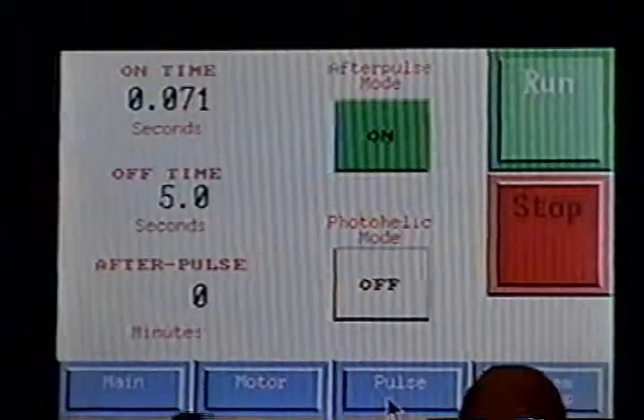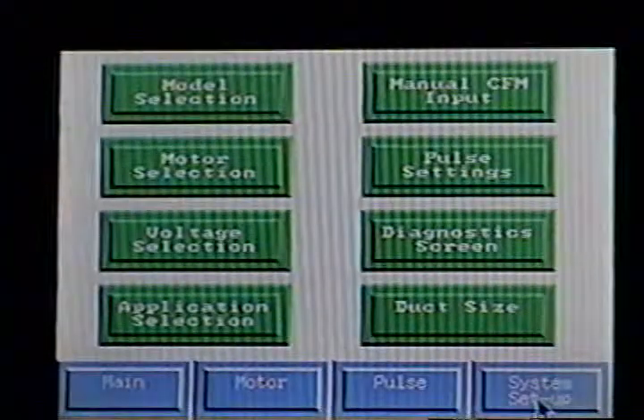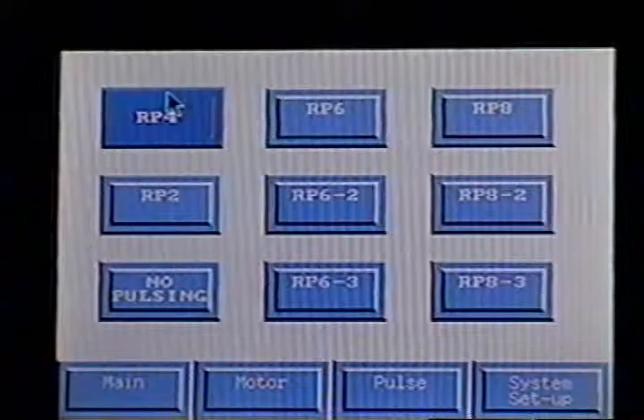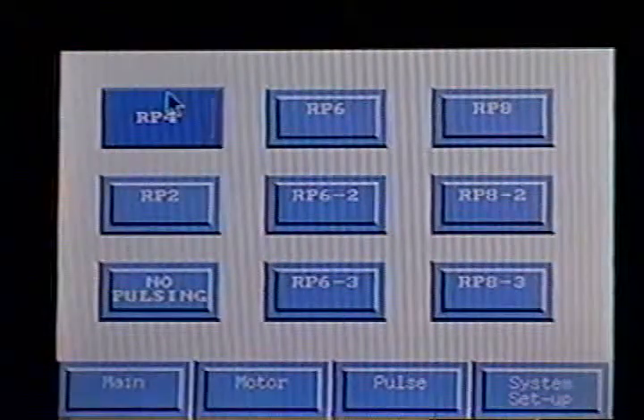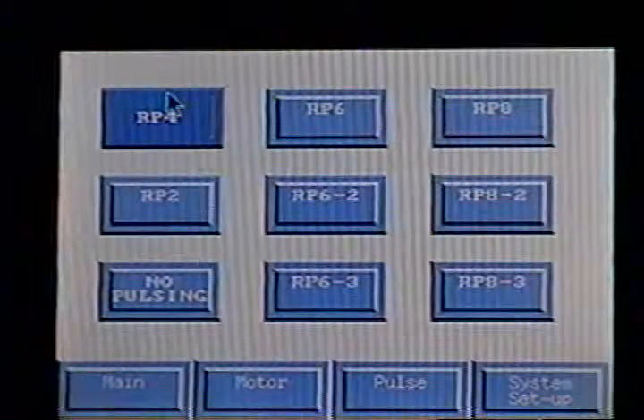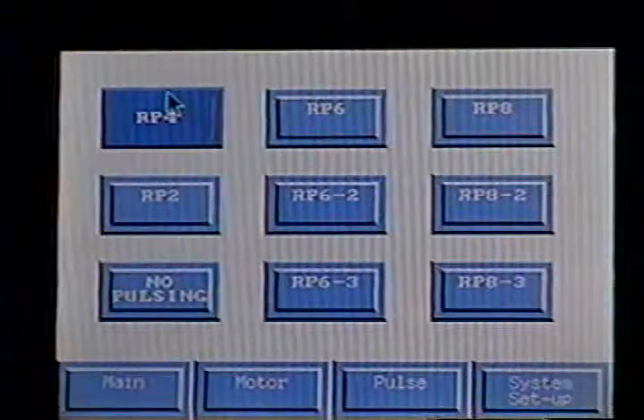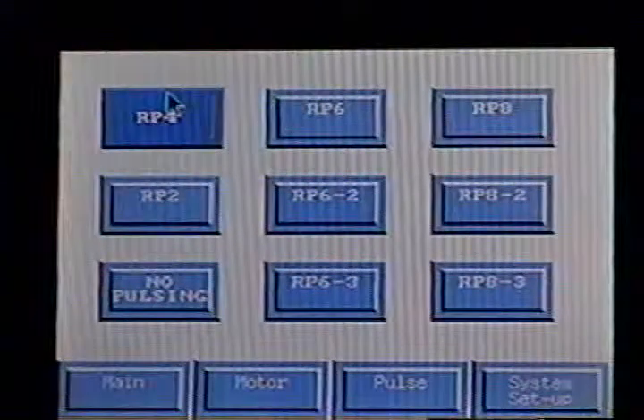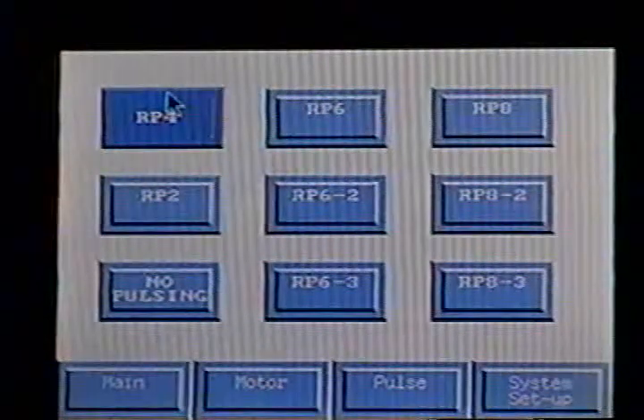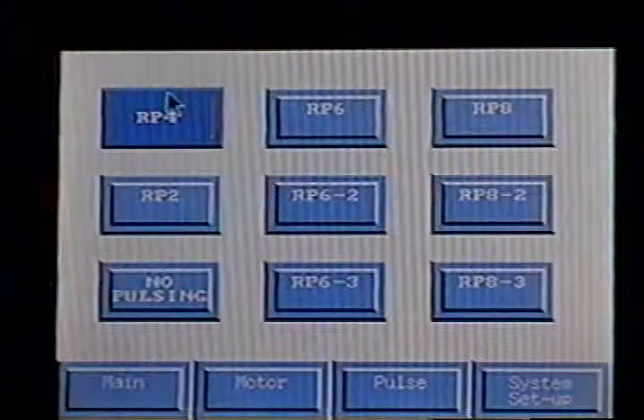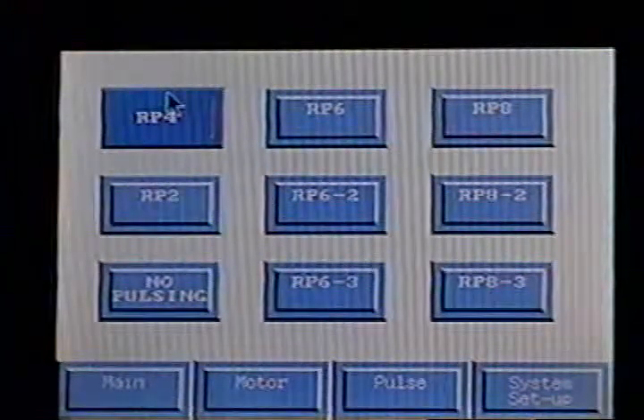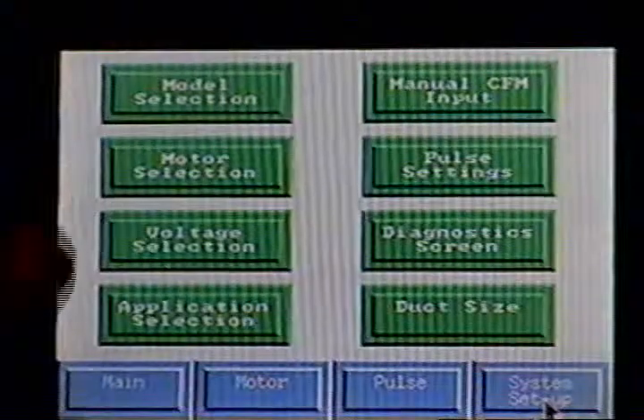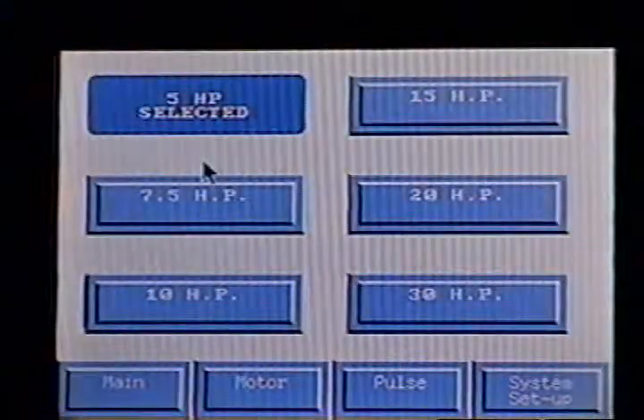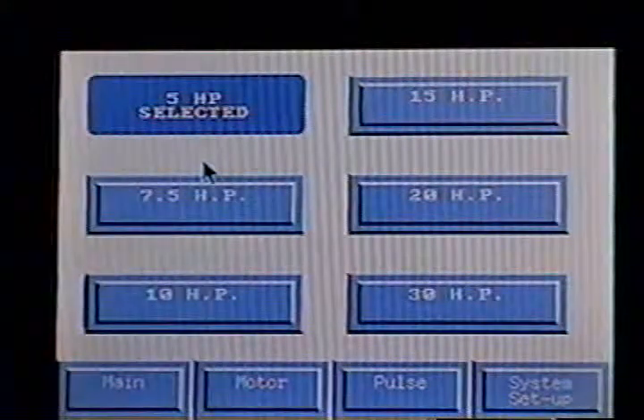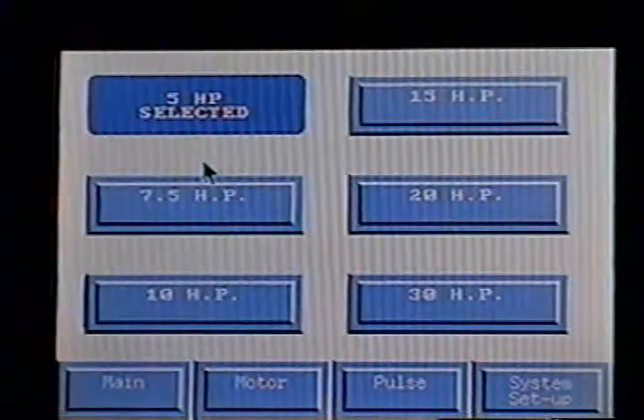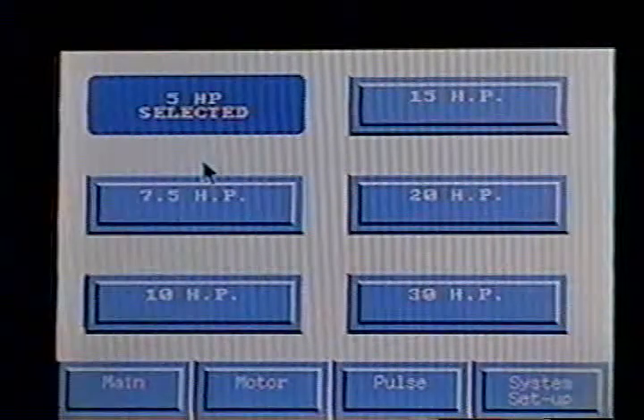We go on to the next one, that's pulsing. Under system setup, these are the model selections available. We've currently set this thing up for all of the RP series, RP2, 4, 6, 8, all the way through. We also have an option just to shut pulsing off completely. That's the no pulsing option. I'm not sure why you'd want to do that, but there may be maintenance issues where you want to shut down pulsing. That's available. It's something you can do. Under motor selection, it's set up to run on the 5, 7, 10, 15, 20, 30 horsepower options. Those are the options that you have available.